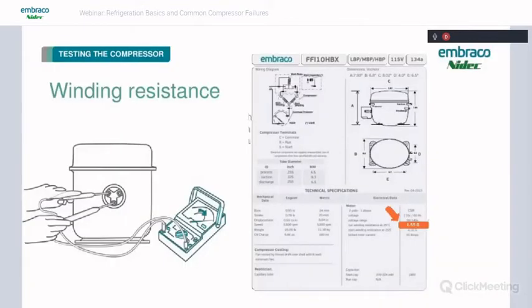So then we can read resistance through the compressor motor and compare it to the spec sheet down here on the right. As you can see, the run winding on this, I believe it says 1.55 ohms, and that's plus or minus 8% at 77 degrees. Just remember, if you've got a very hot compressor, you're going to have a higher resistance reading. If you have the ability to let that compressor cool off, maybe come back and check it and see if it's closer. If you get one that's out of range, let it cool off, see if it's closer when you come back. It's very possible to have one that's showing a bit out of range, out of that percentage, but it still be good because of temperature differences.